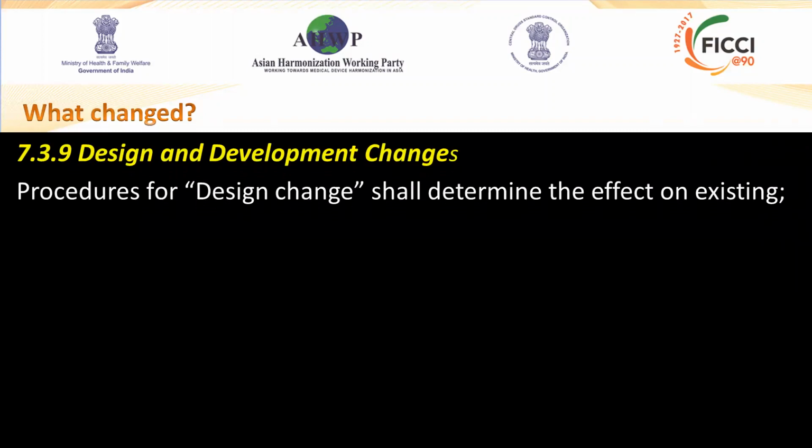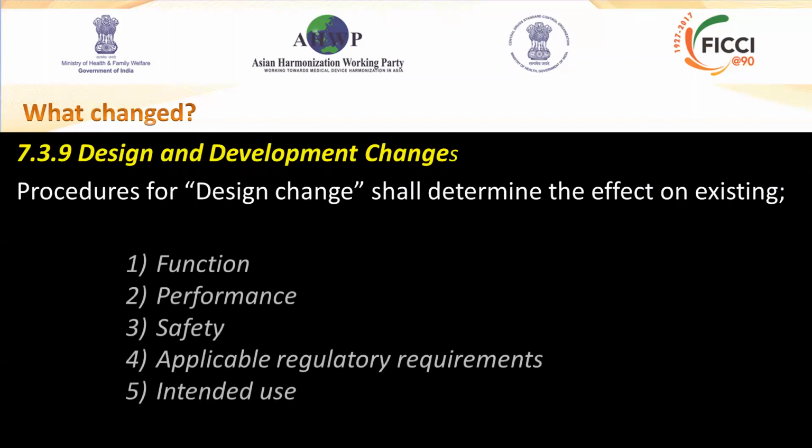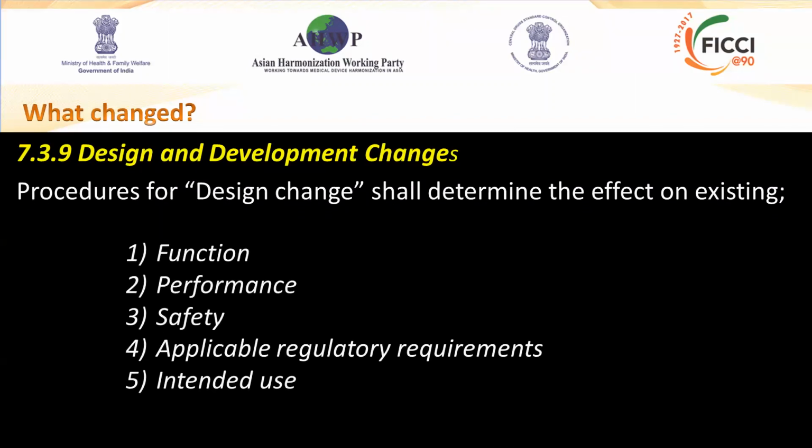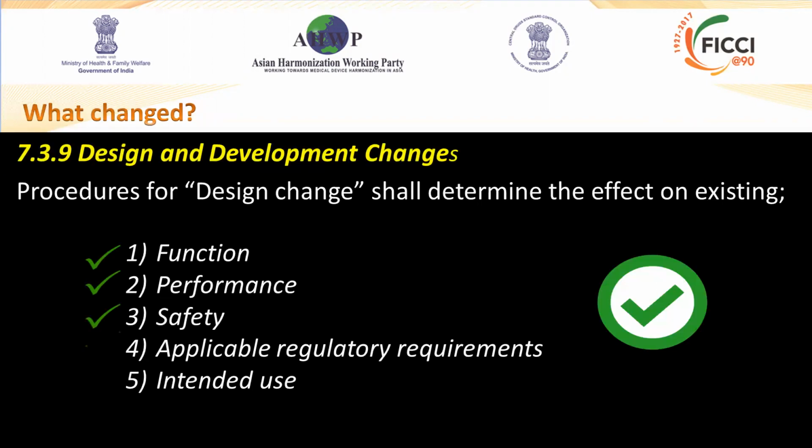Now, design and development changes. Procedures for design change shall determine the effect on existing function, performance, safety, applicable regulatory requirements, intended use. A whole list of things need to be considered when the design change is taking place, and those are detailed in section 7.3.9 of 13485:2016. So a lot more boxes to check when you're doing design changes.